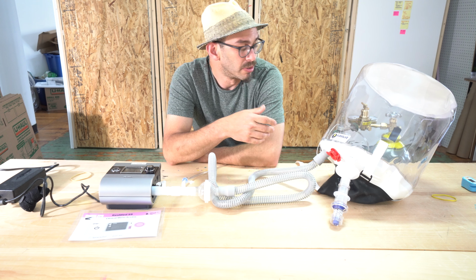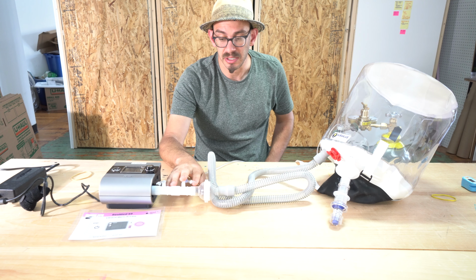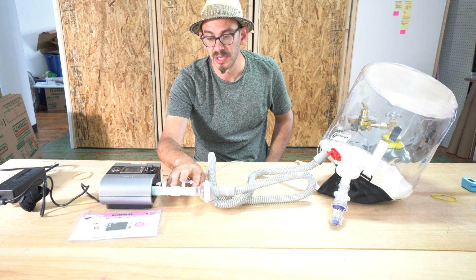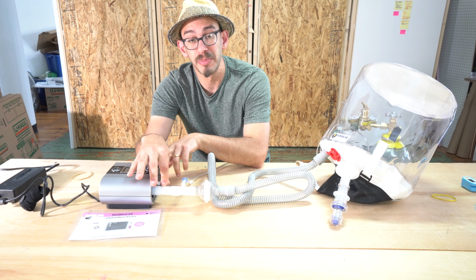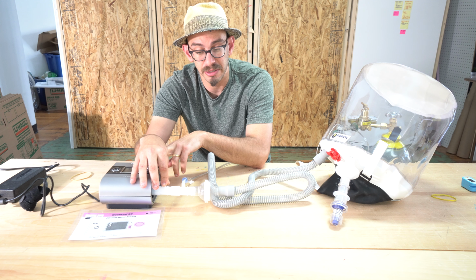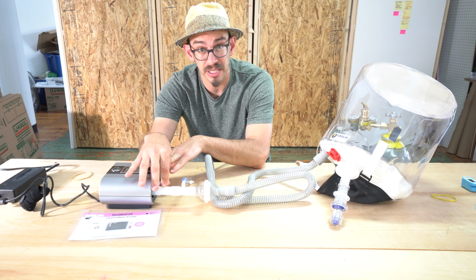In the case that you are running high oxygen flow here and relatively low pressure here, air will come out of the machine and hit your oxygen flow, and that will form like a wall of air. If this opening was not here, there would be a very small amount of air that would be able to flow out of here. The machine could detect a low flow state and turn off. And you do not want that.